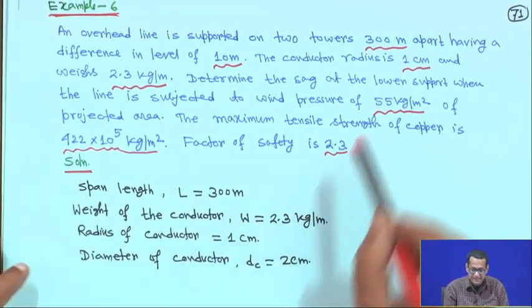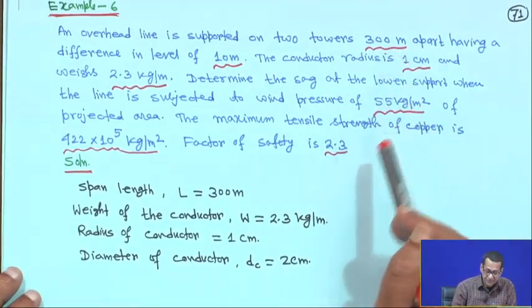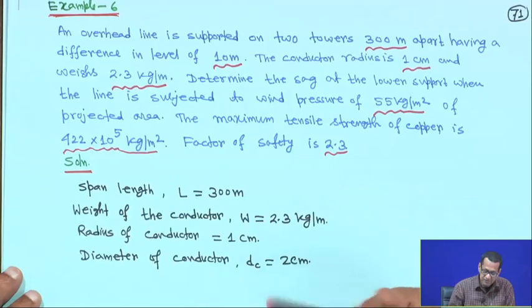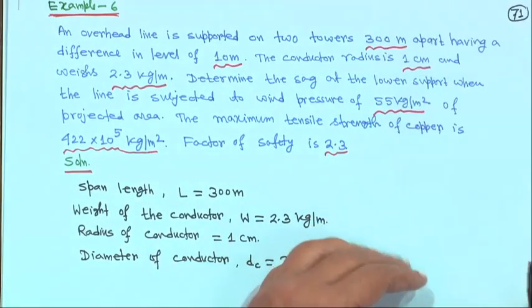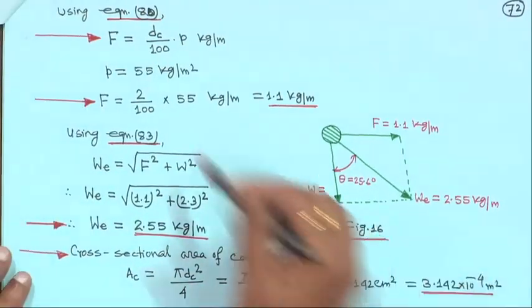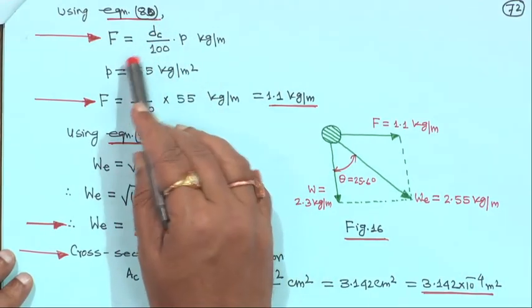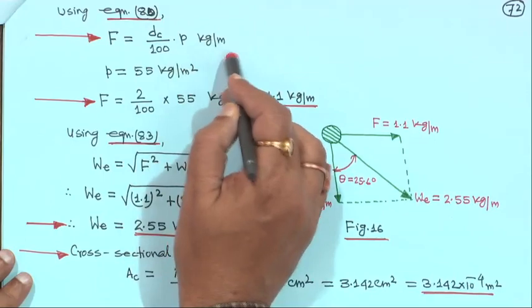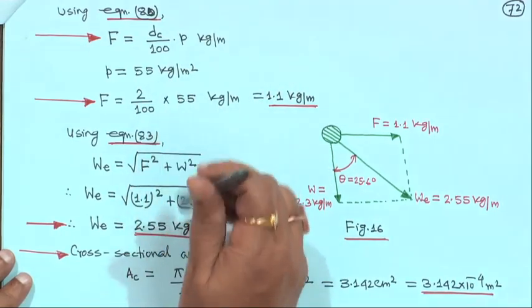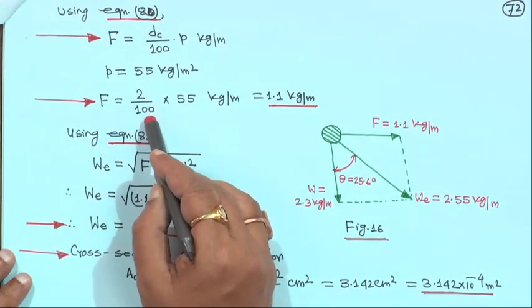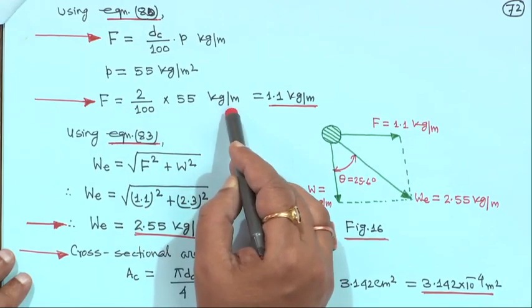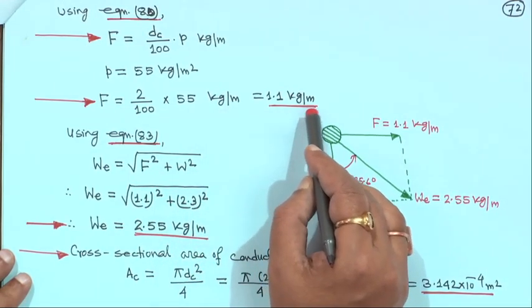Span length L is equal to 300 meter. Weight of the conductor is 2.3 kg per meter. Radius of conductor is 1 centimeter, so diameter DC is 2 centimeter. Using equation 80: F is equal to DC upon 100 into P kg per meter. P is given 55 kg per meter square, and DC is 2 centimeter. So F is equal to 2 by 100 into 55, which gives 1.1 kg per meter.